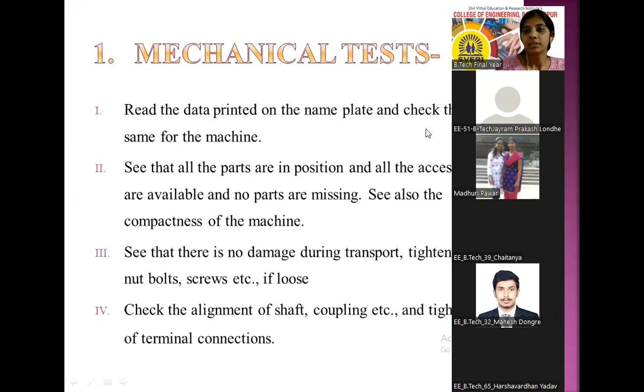Now you can see the various mechanical tests that should be conducted on the machine before selling the product or before getting certification from the Indian standard. Read the data printed on the nameplate and check the same for the machine - as per the performance, if rated speed is given as 15,000 RPM, voltage level etc, all these things you have to check are printed on the nameplate or not. Whenever a customer comes to purchase the machine, they will read the specification, so that data should be printed on the nameplate - some basic information or specifications.